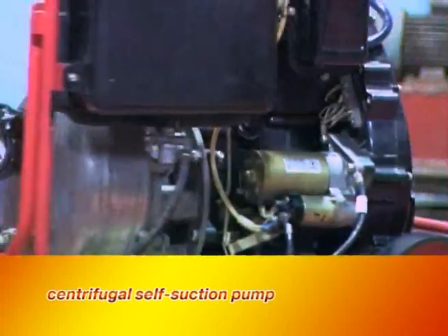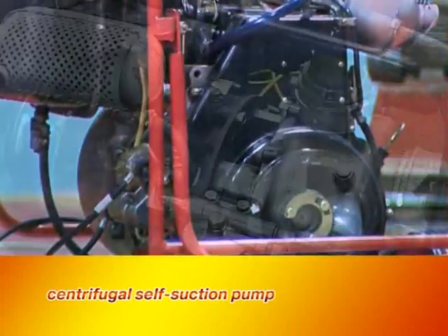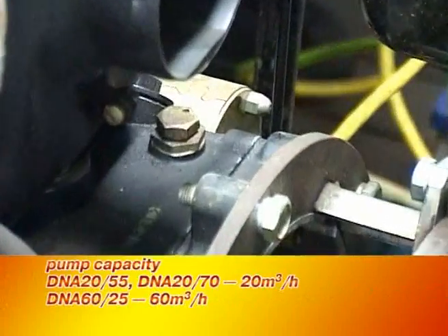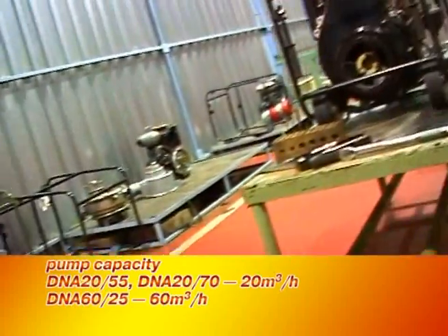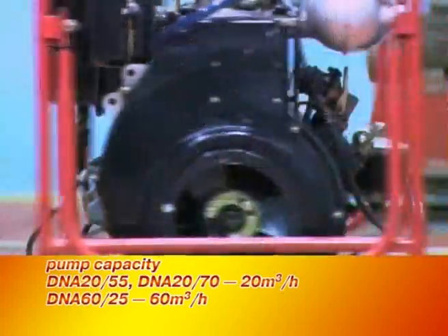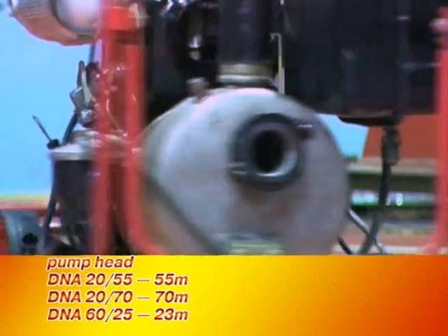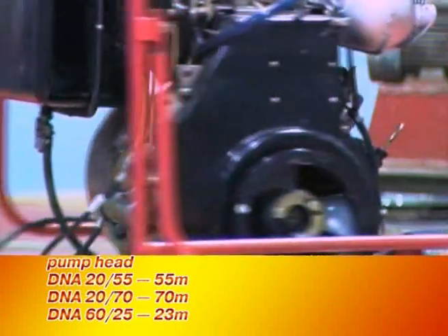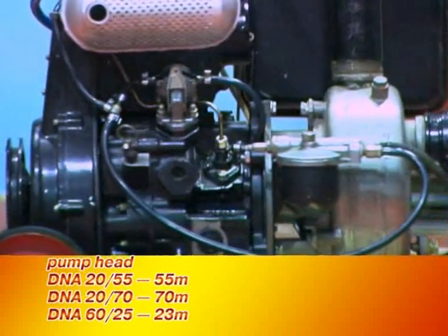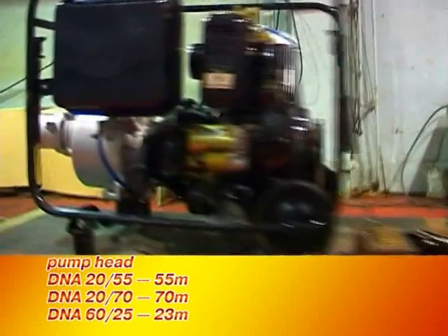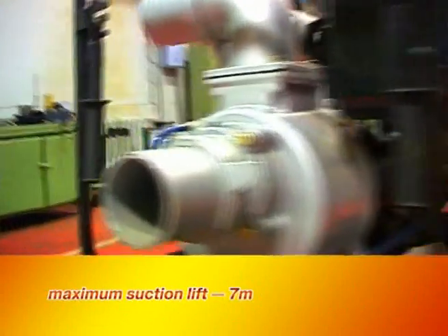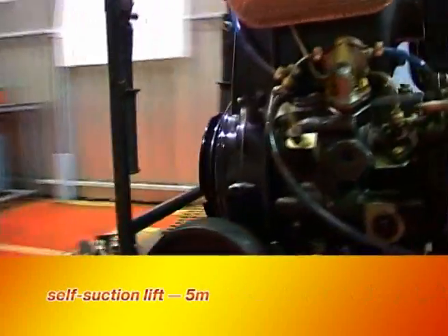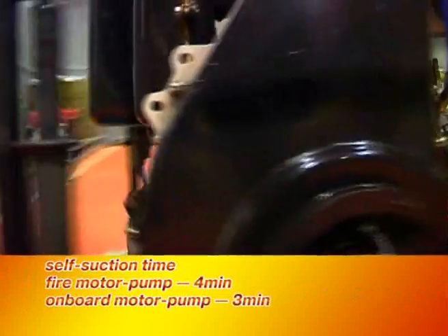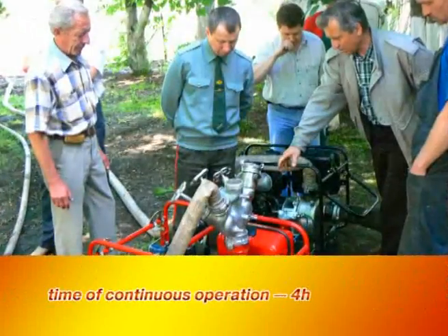Technical data of pumps included into presented motor pumps. All the pumps are of centrifugal self-suction type with one pump impeller and self-suction system with recirculation. During operation under rated conditions, efficiency is 20 cubic meters per hour with fire motor pumps and 60 cubic meters per hour with overboard pumps. Pump head under rated condition is 55 meters for DNA 20/55 pump, 70 meters for DNA 20/70 pump, and 23 meters for DNA 60/25 pump. Maximum suction lift is not less than 7 meters. Self-suction lift under rated conditions is 5 meters. Self-suction time under rated conditions is 4 minutes for fire motor pumps and 3 minutes for onboard motor pump. Time of continuous operation without refueling is 4 hours.